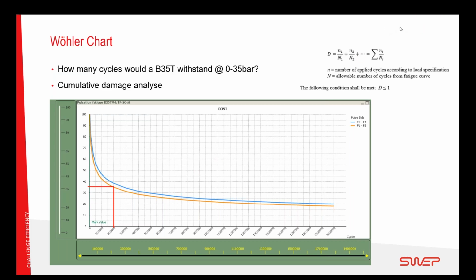This chart we can also use for cumulative damage analysis to predict a lifetime. Depending on how accurately we can define the operating conditions, for example for a condenser for a heat pump, depending on which mode, whether it's running for heating or running reversed for cooling, what pressures it will be operating at, and then going into defrost mode. If this can be specified over a 10-year cycle, you can see how many cycles, and you add it up together: the number of applied cycles divided by how many cycles are allowed, taking the number from the fatigue curve, and you add those up together. You should not, of course, exceed 100% of the capability of the heat exchanger. So that's one way to estimate the lifetime from mechanical pulsation fatigue.